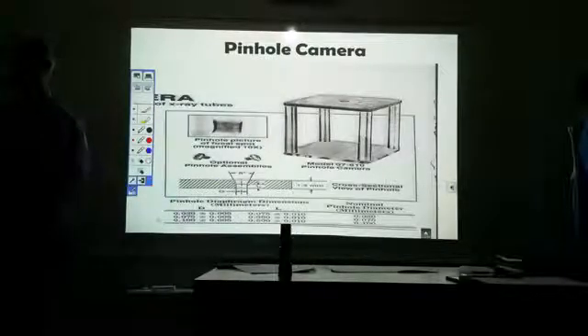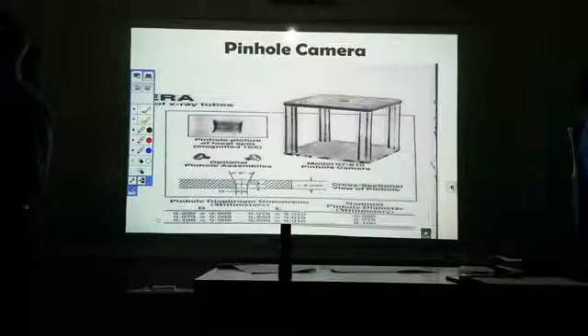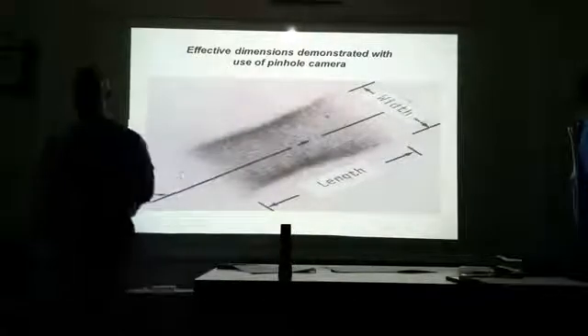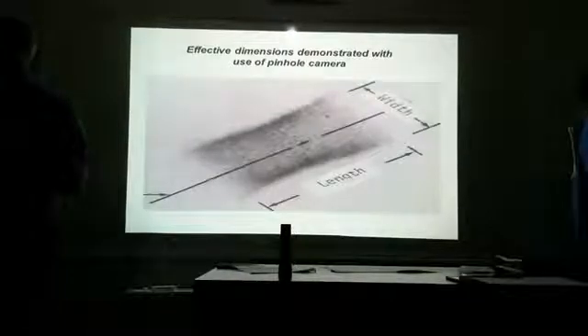The pinhole camera does the same thing. We're going to put the x-ray on top of the hole, take an x-ray of it, and then develop the film. The developed film will have the exact dimensions of the focal spot size — same concept. That's using a pinhole camera. And we already know about the resolution test pattern and line pairs.